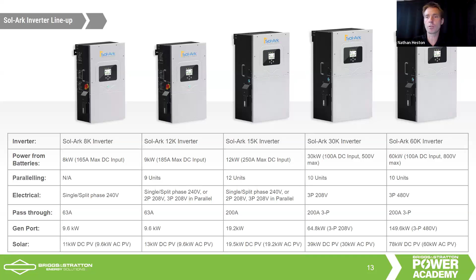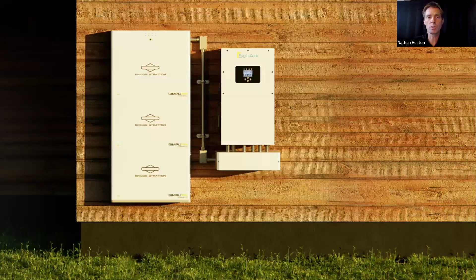With the Sol-Ark 15K, if you combine multiple inverters, you can parallel up to 12 inverters and also do 208 output with the 15Ks and 12Ks. You can do 208 with as little as 2 inverters for 3 legs, but if you want a balanced system, you should use 3, 6, 9, or 12 inverters for 208 applications.